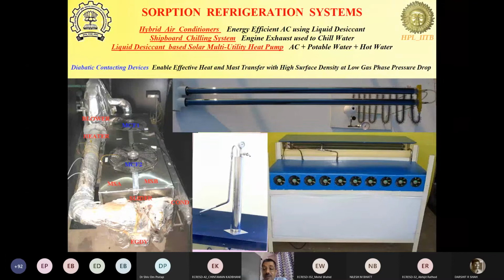And this increased evaporator temperature increases the evaporator pressure. Increased evaporator pressure leads to reduced pressure ratio. Reduced pressure ratio leads to improved COP and increased capacity also. So we'll see some of these advantages when we look at the detail.